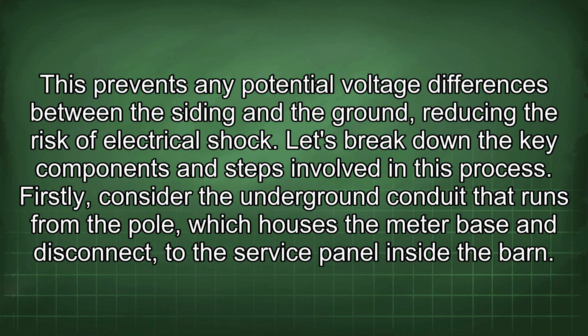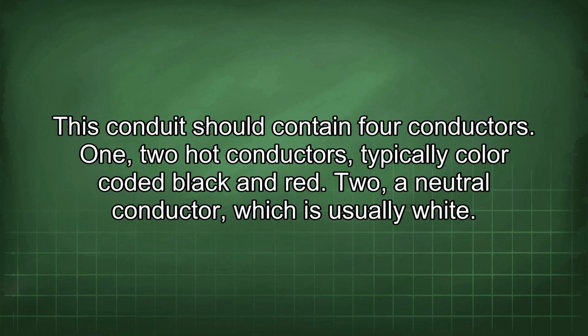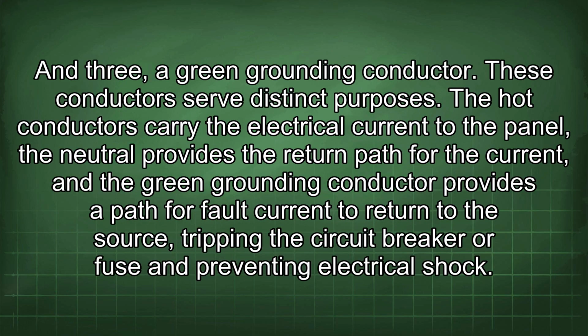Let's break down the key components and steps involved in this process. Firstly, consider the underground conduit that runs from the pole, which houses the meter base and disconnect, to the service panel inside the barn. This conduit should contain 4 conductors. 1. 2 hot conductors, typically color-coded black and red. 2. A neutral conductor, which is usually white. And 3. A green grounding conductor. These conductors serve distinct purposes. The hot conductors carry the electrical current to the panel, the neutral provides the return path for the current, and the green grounding conductor provides a path for fault current to return to the source, tripping the circuit breaker or fuse and preventing electrical shock.